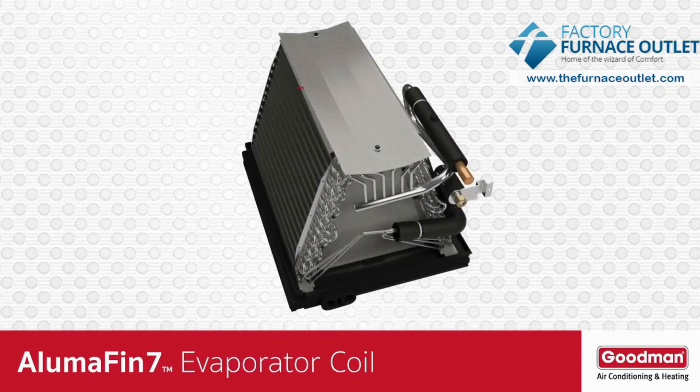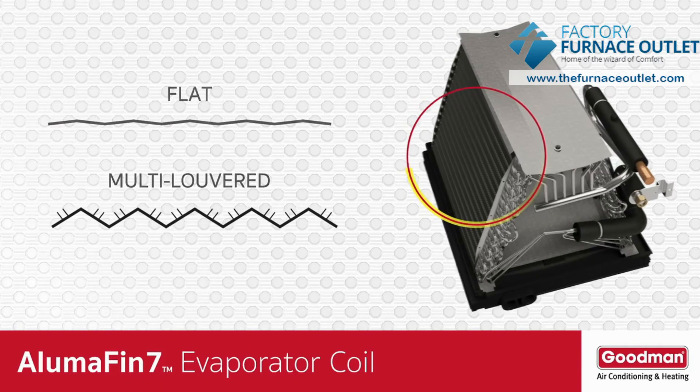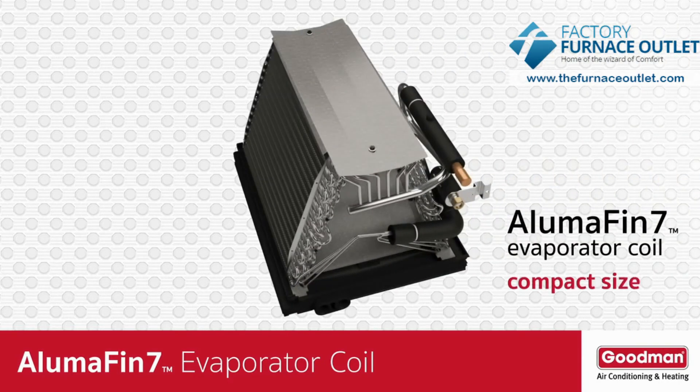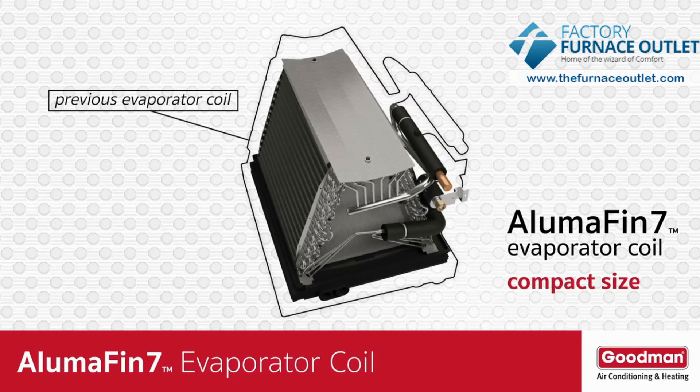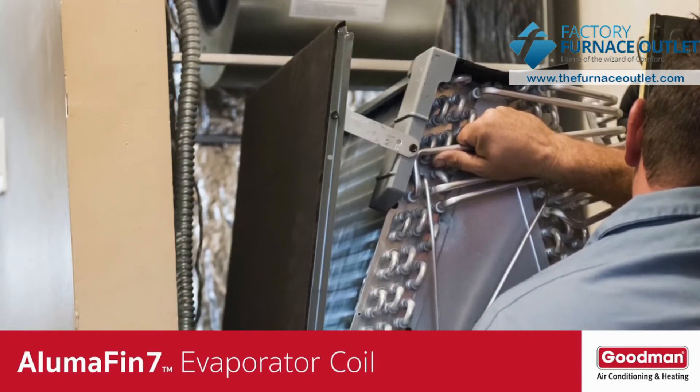Speaking of surface area, the fins on an AlumaFin7 evaporator coil are not flat — they're multi-louvred. These louvers help to create more opportunities for the warm, humid air to lose water vapor. Another benefit of the small size tubing and multi-louvred fins relates to the physical size of the AlumaFin7 evaporator coil. The smaller tubing and multi-louvred fins allow the evaporator coil to be smaller in total size without a loss of performance, which can be really important if your local HVAC dealer needs to install the coil in a tight space.